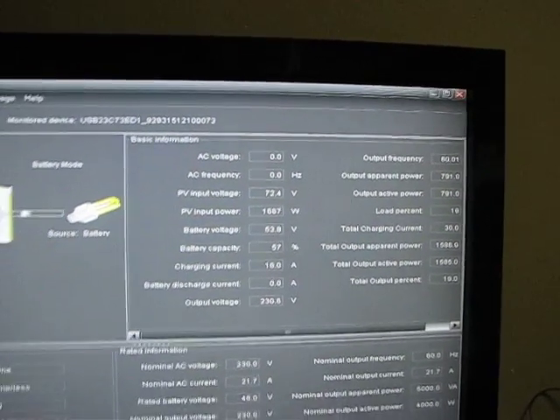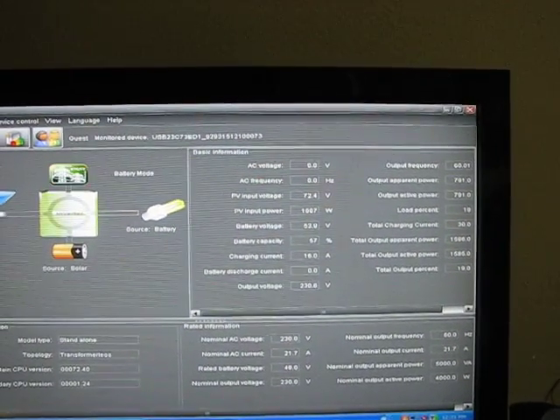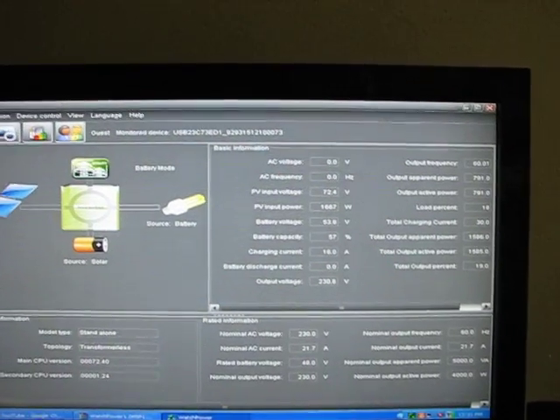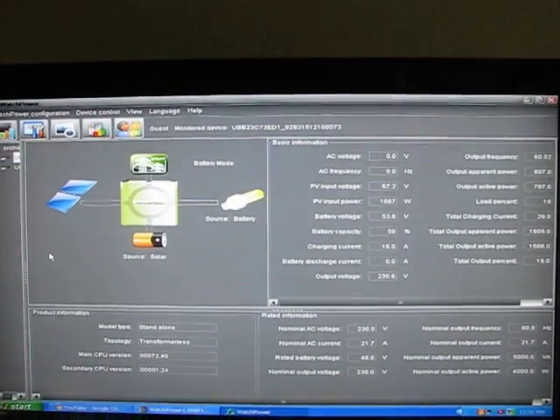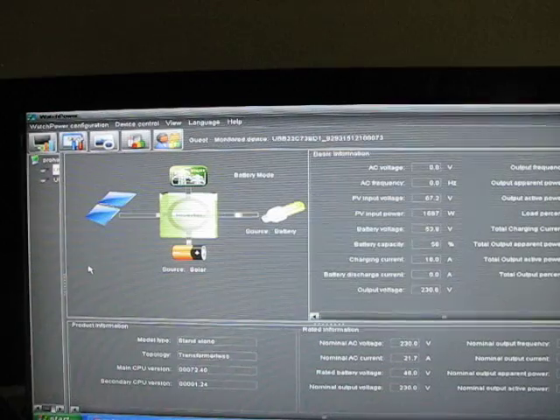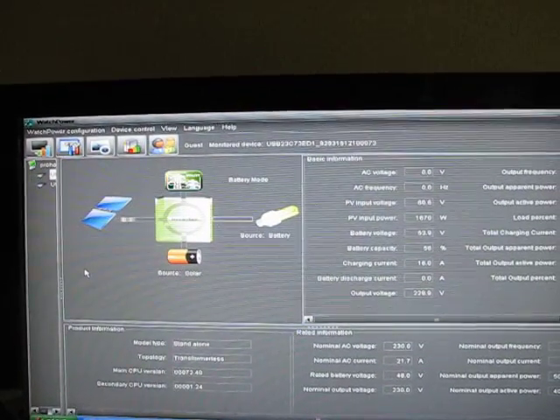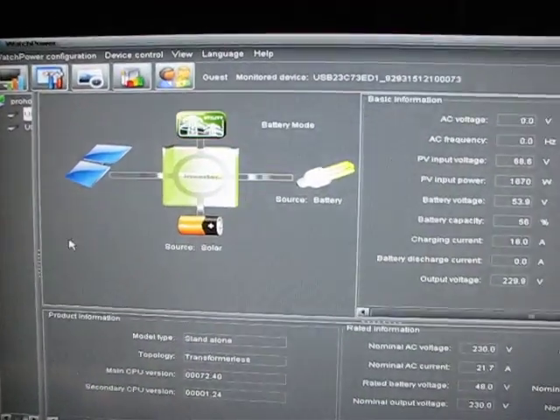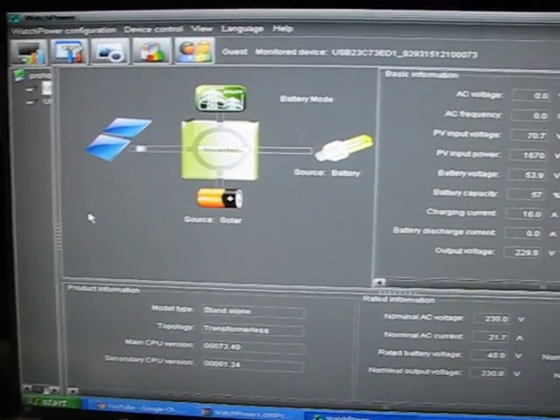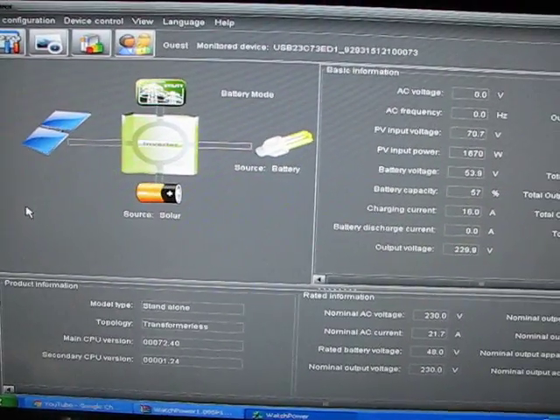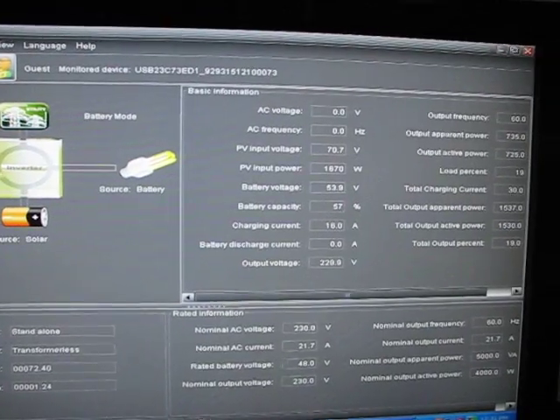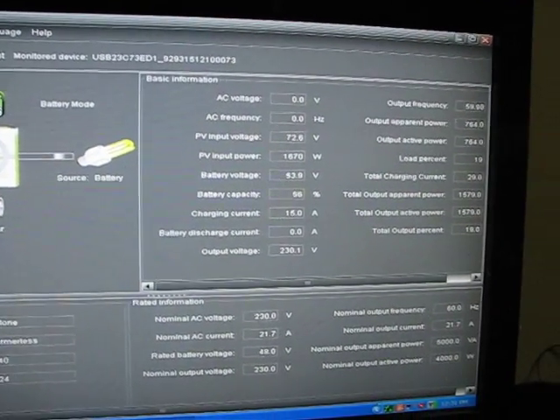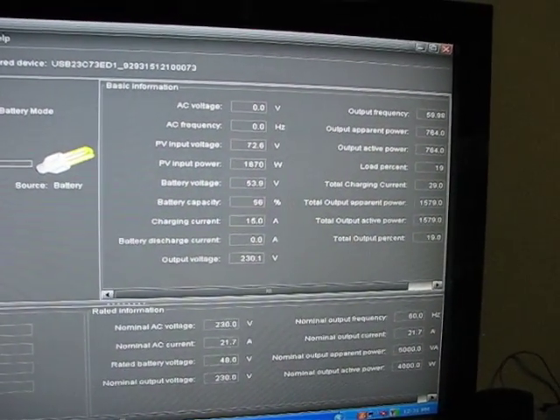And then still on the batteries, it only drops one volt overnight on average, from about 53.3 to about 52.2, somewhere in there, about a volt. That's on a heavy usage night. And then on a good night, you know, it'll drop less than a volt.